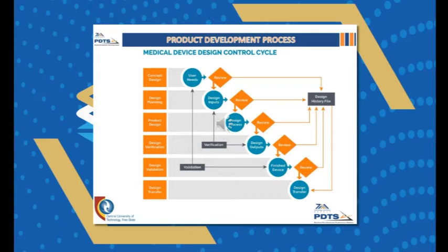Different methods can be used for design verification. Either testing, team reviews, or demonstration, to ensure that the requirements have been met. Once the verification has been done, you also need to check that the design meets the intended use. This process is called design validation.